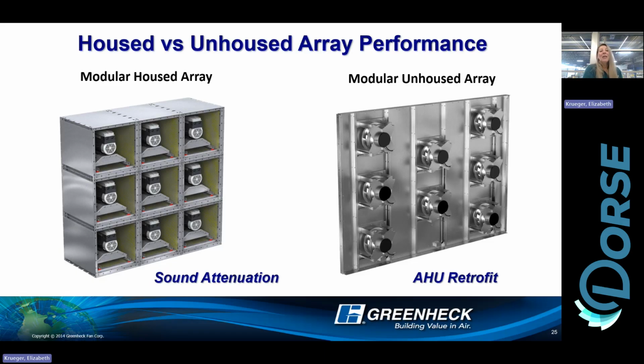All right, so looking at our housed array, pretty simple setup. We have controls again for both available. We actually just came out with controls for our housed array to interface with those EC titanium motors. You can see those motors in there. Those are the style that have the built-in VFD in them. They're 1 to 15 horse available. So really, you could pick either depending on the application.